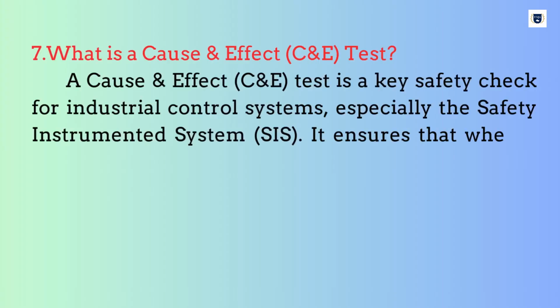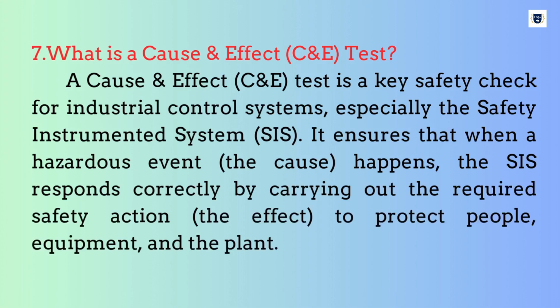What is a cause and effect test? A cause and effect test is a key safety check for industrial control systems, especially the safety instrumented system. It ensures that when a hazardous event happens, the safety instrumented system responds correctly by carrying out the required safety action to protect people, equipment, and the plant.